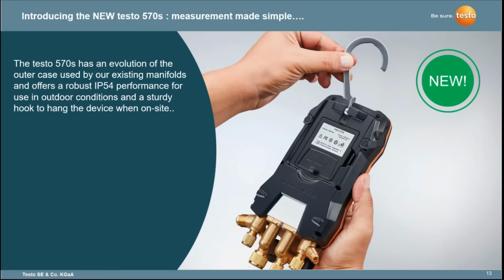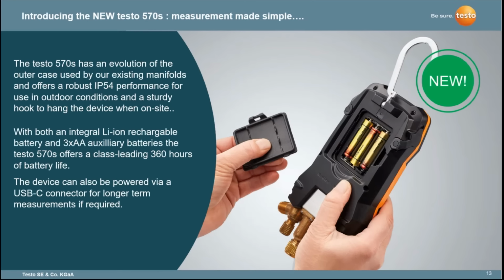So this 570 is an evolution of our current manifold range, and with the 55X range, we introduced a new style of design and construction. Very, very robust IP54 performance, so it could be used in outdoor conditions with rain, water spray on the device. Very sturdy hook to hang the device when on site. One of the key differences with the 570s against our other products, though, is the fact that it has both an integral lithium-ion rechargeable battery, but also has this option of running it off some AA auxiliary batteries to lengthen the battery runtime.